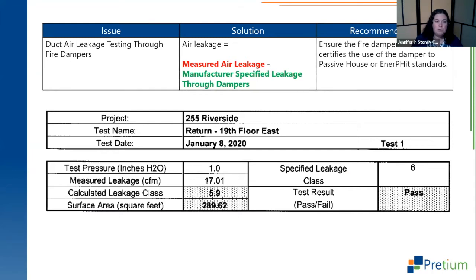One thing that we found when we went to do pressure testing of the duct was that particularly the fire dampers, when we were testing the runs for the vertical riser, because they're basically every 7 or 8 feet, depending on the floor to ceiling height, were having a pretty significant impact on our testing. And the fire damper manufacturer was not very comfortable at all with us testing these fire dampers via the pressure test the way that we were hoping to.